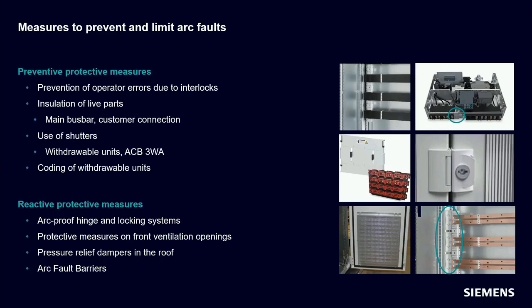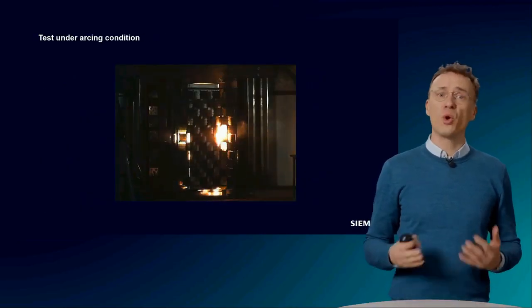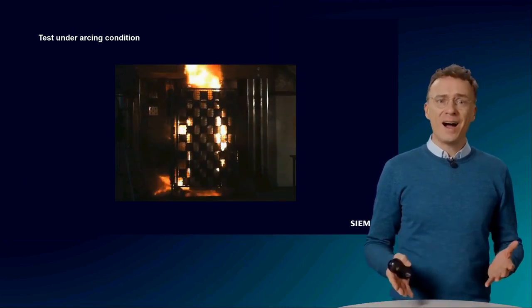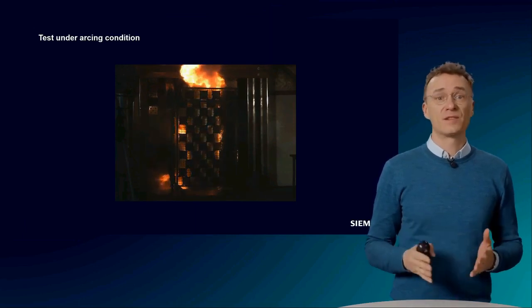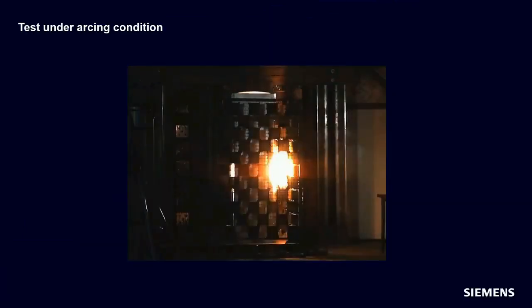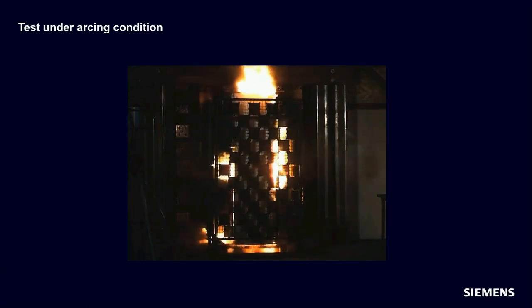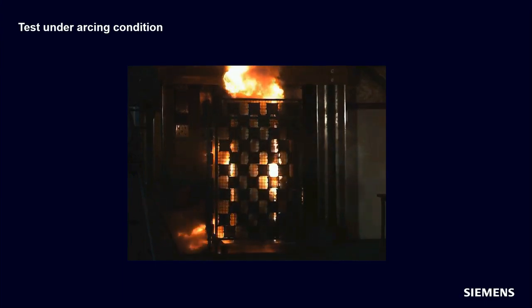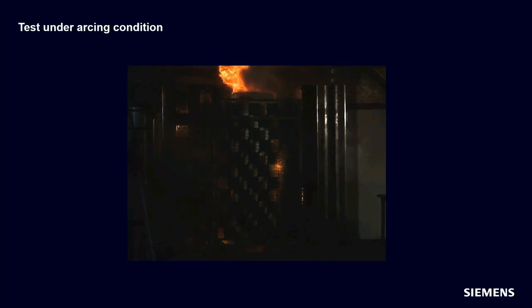But is that all enough? As always, it depends on what is to be achieved. The requirements of IEC Technical Report 61641 can be met in any case. However, when limiting the arc fault with the help of passive measures, an arc flash burning time of 300 milliseconds can be expected. This duration means a very high energy conversion.